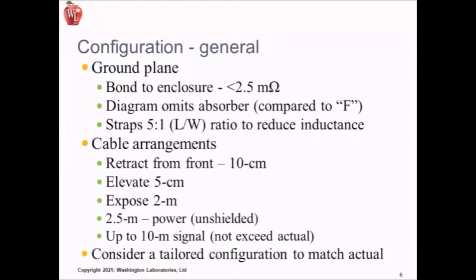So in general, the ideal is to bond the ground plane to the enclosure with a very low resistance or low impedance connection, again, to stabilize the test environment. The ground straps are prescribed to have a length to width ratio of at least 5:1, and this is intended to reduce the high frequency inductance of the strap so you can maintain a low impedance connection. Cable arrangements are prescribed 10 centimeters back, elevated by 5 centimeters above the ground plane, and expose at least 2 meters of cable to the antenna. And this is designed to get a reasonable amount of energy that you're detecting from an antenna, and you're also exposing a sufficient amount of the cable to couple when you're doing radiated susceptibility tests.